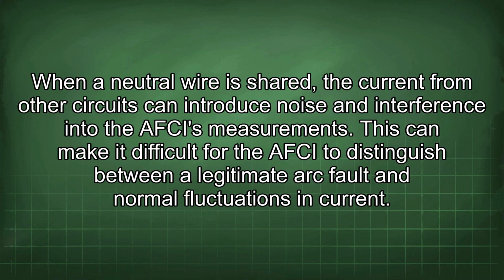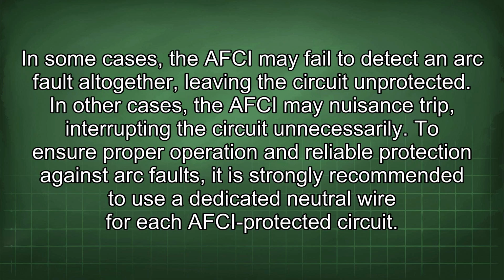When a neutral wire is shared, the current from other circuits can introduce noise and interference into the AFCI's measurements. This can make it difficult for the AFCI to distinguish between a legitimate arc fault and normal fluctuations in current. In some cases, the AFCI may fail to detect an arc fault altogether, leaving the circuit unprotected. In other cases, the AFCI may nuisance trip, interrupting the circuit unnecessarily. To ensure proper operation and reliable protection against arc faults, it is strongly recommended to use a dedicated neutral wire for each AFCI protected circuit.